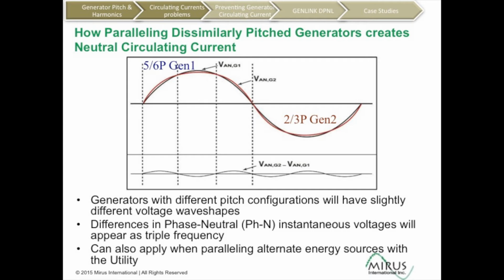By the true definition of harmonics, however, this is not a third harmonic. Harmonic is the result of Fourier analysis on a distorted waveform. This is simply voltage that has a frequency that is 3 times the fundamental that results from the voltage wave shapes being dissimilar. I know it's a bit of semantics, but this is what we're dealing with more, the dissimilar voltage wave shapes. I highlight that particularly because we're finding that people constantly say 2/3 pitch is better because it doesn't generate third harmonic voltages.